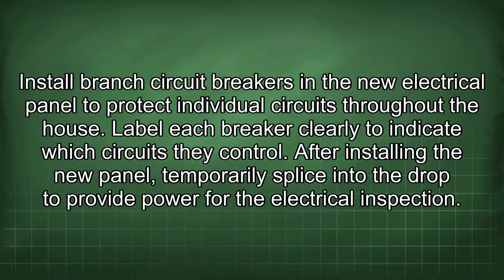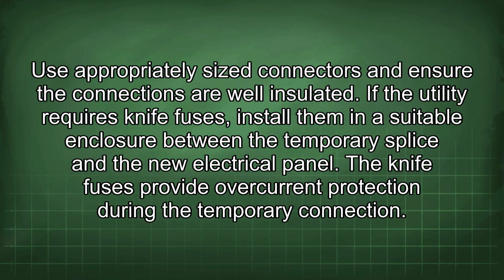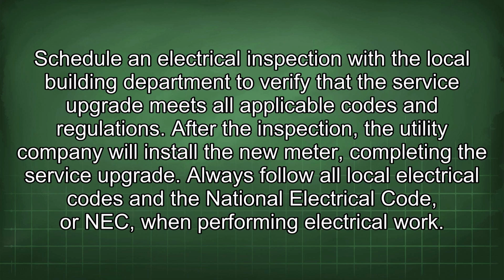After installing the new panel, temporarily splice into the drop to provide power for the electrical inspection. Use appropriately sized connectors and ensure the connections are well insulated. If the utility requires knife fuses, install them in a suitable enclosure between the temporary splice and the new electrical panel. The knife fuses provide overcurrent protection during the temporary connection. Schedule an electrical inspection with the local building department to verify that the service upgrade meets all applicable codes and regulations. After the inspection, the utility company will install the new meter, completing the service upgrade.